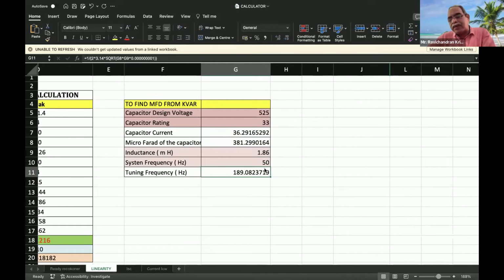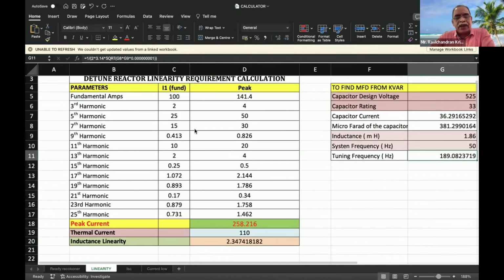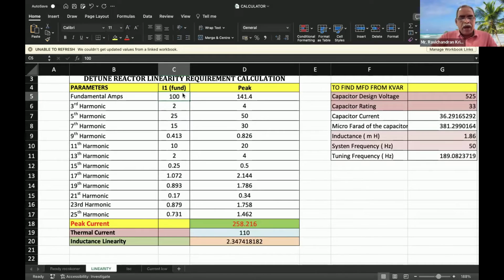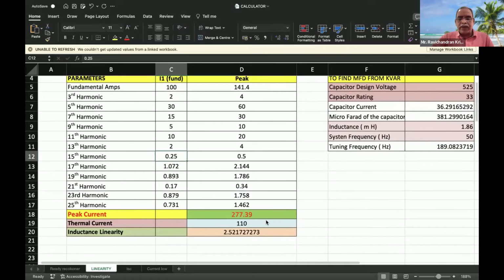But the current handling capacity of the reactor, no one is worrying about, because of linearity. For the standard reactor, only 1.6 or 1.8 is available in the market. Linearity is the important key factor. For the individual order harmonic components, see this: the fundamental is 100 ampere. I am putting 30 ampere here, and the seventh is, for example, 15 ampere. The ninth is 5 ampere, like that I am putting, and adding all the values here. The linearity comes to 2.52.